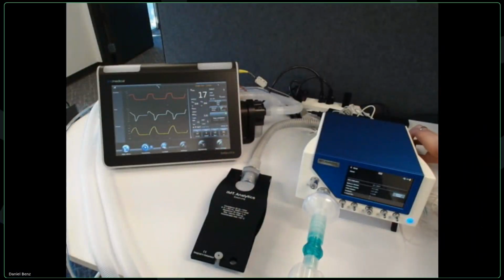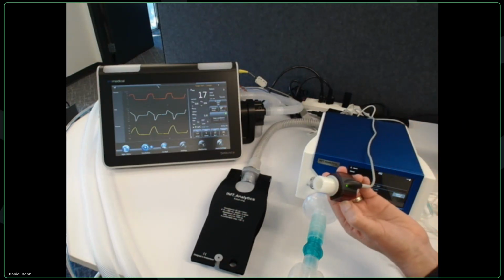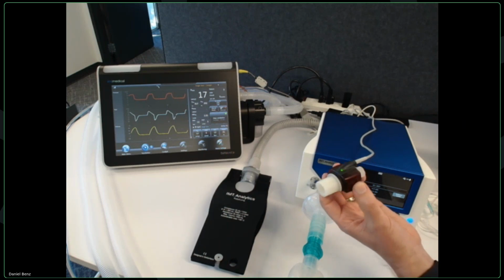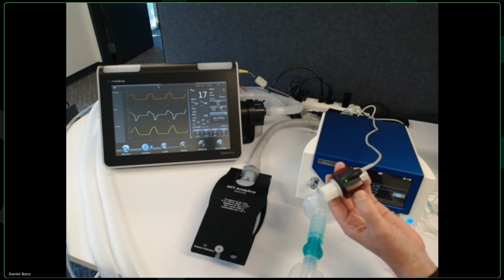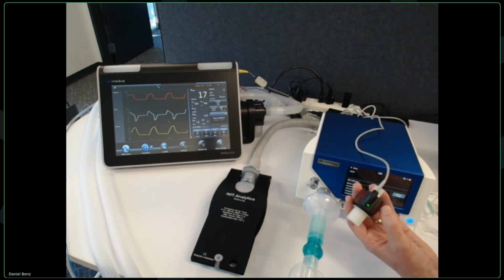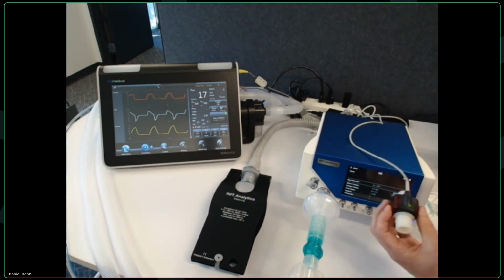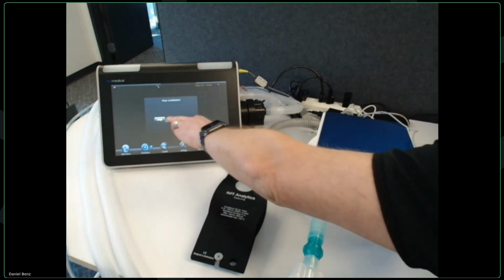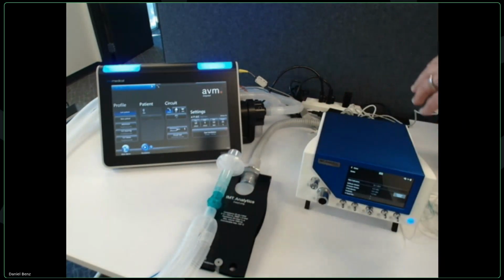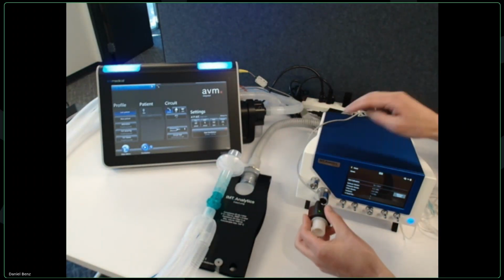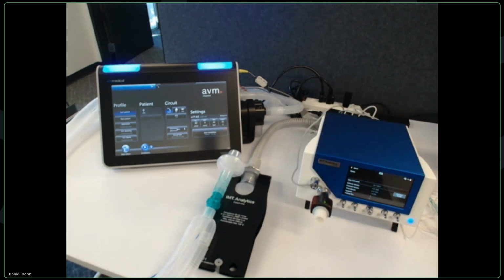And as mentioned earlier, we offer an optional accessory, which is our anesthetic gas analyzer. It's called the OR703 multi-gas analyzer. So this is how it looks. I have one here connected to my device. It is a small optical bench that can measure all the anesthetic gases concentration, as well as CO2 and N2O. If I want to use that one, I just connect it to the back side of the device. There is an RS-232 interface, and it's a mainstream sensor, so I can connect it just to my main flow channel, just like so, in front of my device. And then I connect my circuit with the gas flow right here. So this just goes in between the main flow channel and your circuit.